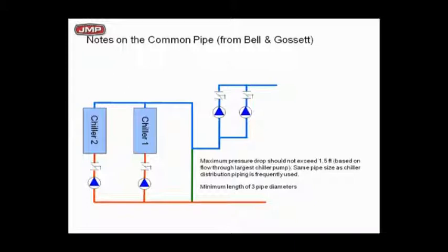And the comment came back: let's make it a minimum of three pipe diameters and let's keep the pressure drop to less than a foot and a half. You're not going to have any problems. So there's your answer: three pipe diameters minimum, keep it a foot and a half pressure drop, you will not have any mixing problems.